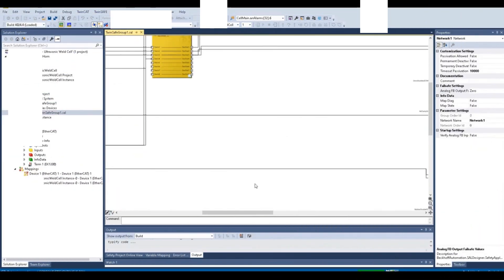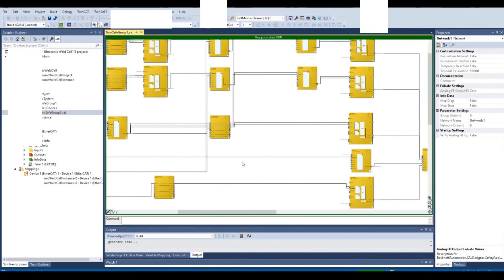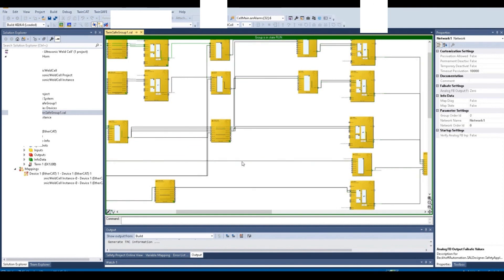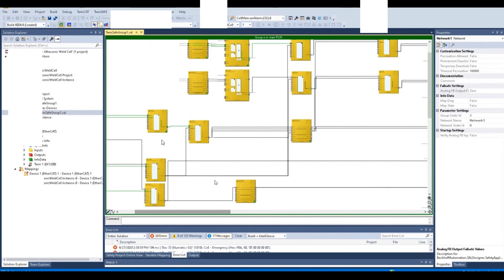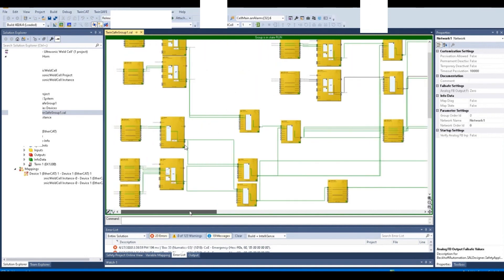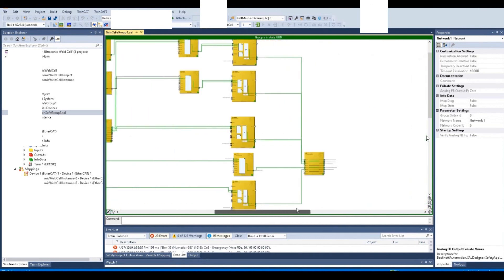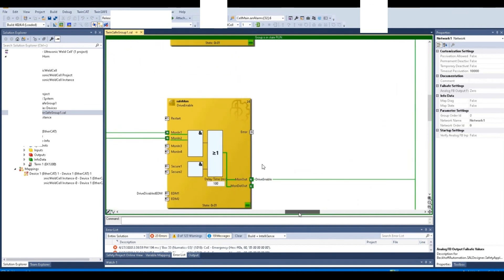This is the global view of the whole TwinSafe safety logic. If we go online, we can see the signal flows. If the e-stop is pressed, we will see the output go off, and once the e-stop recovers we will see the signal flow recovered. We can clearly see the signal flows, and with this signal flow view it is very easy to troubleshoot.